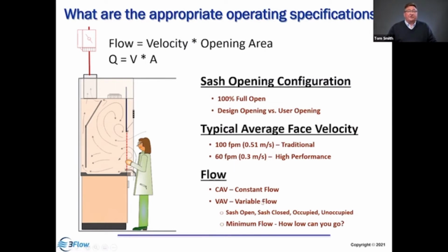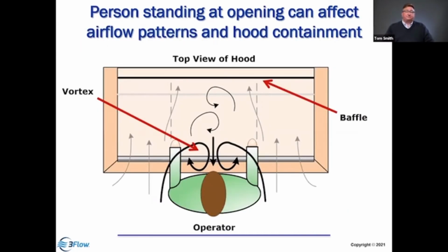And then is the flow going to be constant regardless of sash position, 24 hours a day, 7 days a week, or is it variable air volume, which means it may modulate flow depending on its operating mode, occupied, unoccupied, sash open, sash closed, and how low can we go when the sash is closed. We may still have processes and procedures in the hood.